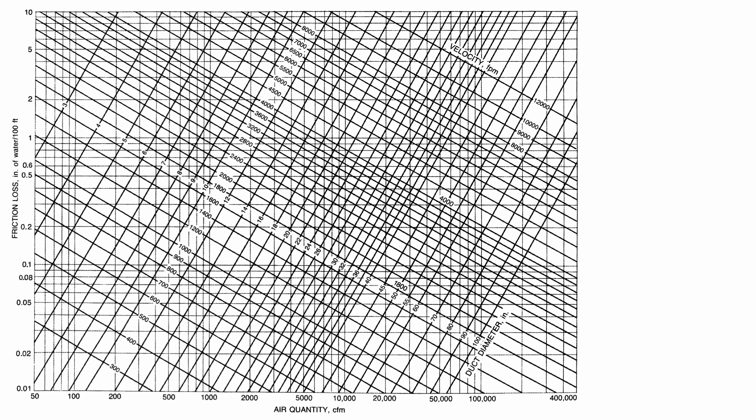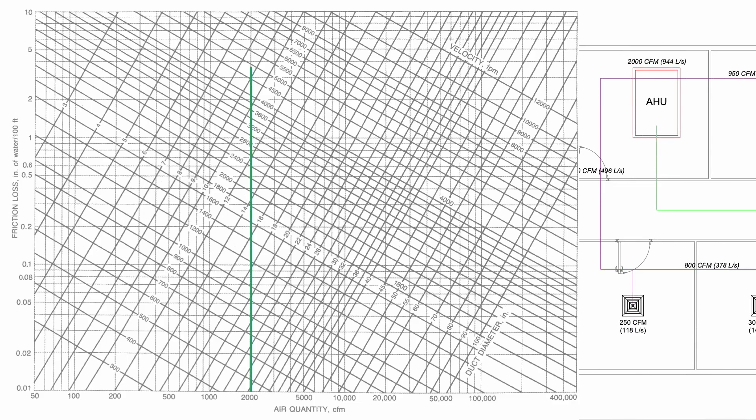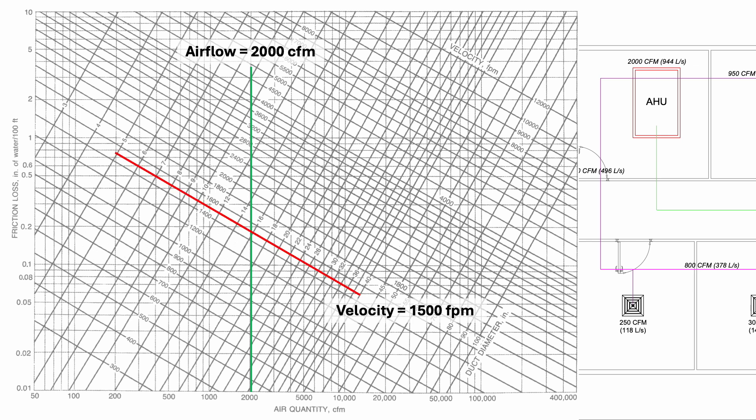A very easy way to size duct is using the friction loss chart. You can find the link to download this friction loss chart in the video description. We start at the AHU. The airflow is 2000 CFM. Then, we limit the velocity at 1500 feet per minute.